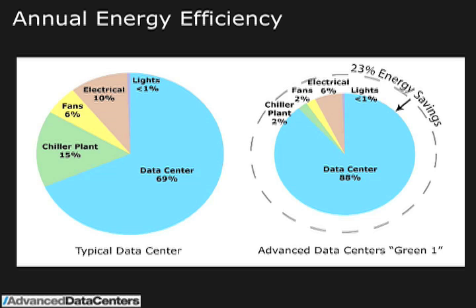So when we look at the typical data center, and this would be that PUE of 1.4, 1.5, the IT equipment would be about 70% of the energy use. What we're doing here is trying to squeeze out the chiller and the fan and the electrical losses so that we can get 80, 90% of the electrical use going to the useful work that we're trying to do in a data center.